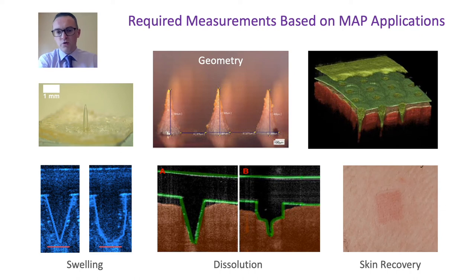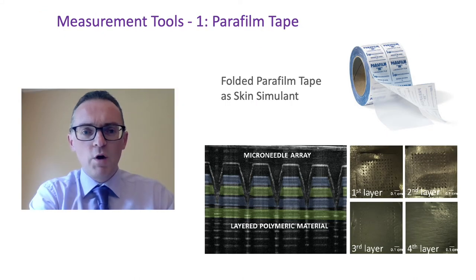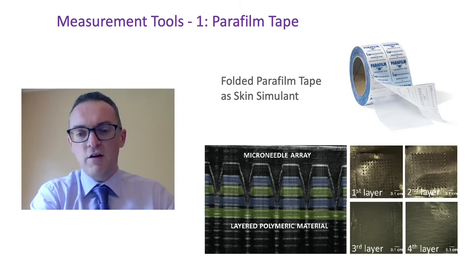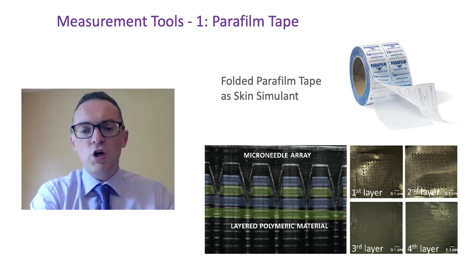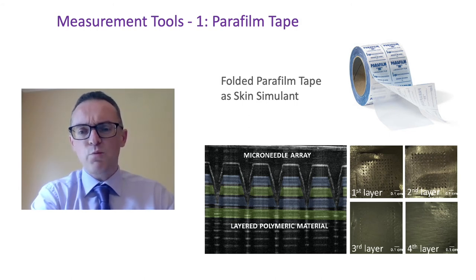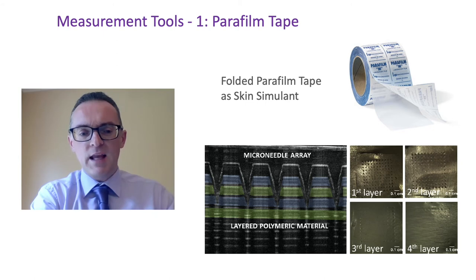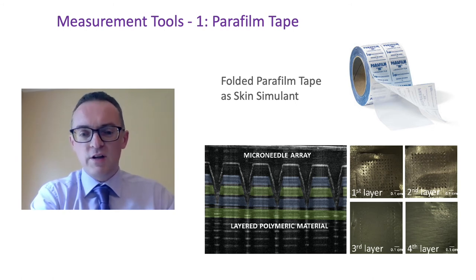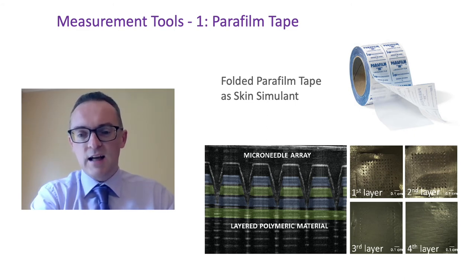One measurement tool that we have found particularly useful is the simple use of parafilm, which is found in every laboratory in the world for sealing containers. At the time, we were looking for an artificial membrane to mimic skin behavior and looked at various silicone elastomers. What we found was that they would typically indent, but when the microneedle was removed, they would just pop back up, so we couldn't measure penetration depth.